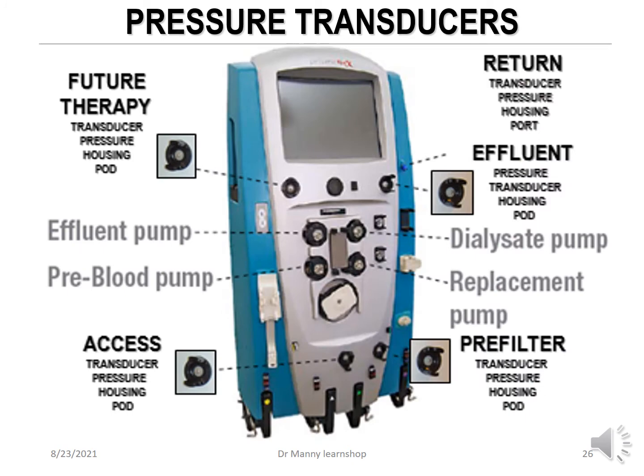You've got pressure transducers. The one on the left hand side really doesn't do anything currently, it's for future therapy. Then you've got the return pressure transducer, which measures the return line pressure. The effluent pressure transducer measures the pressure created to create the effluent. The pre-filter transducer determines how much pressure it requires to deliver the pre-filter fluid. And you've got the access transducer, which tells you what sort of negative pressure you're creating to pull out the fluid. And these are all in conjunction with the different pumps that you've got, which the four that you can see.